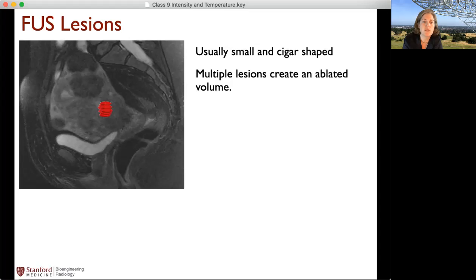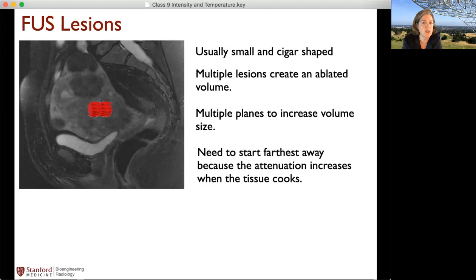Then if you wanted to increase the volume, you might increase the volume in that plane, scanning around and making more in that plane. But if you wanted to have another plane, then you have to come forward towards the transducer, and you would do the same thing again. You always want to ablate farthest from the transducer and then move towards the transducer, because when the tissue is ablated, the absorption increases. There'll be more attenuation because there's more absorption. And so getting past a thermal lesion to an area that's past it is harder to do because the attenuation has gone up. And you may not get a very good focal spot past a thermally ablated area. So typically what happens is you go farthest from the transducer and then move forward towards the transducer.